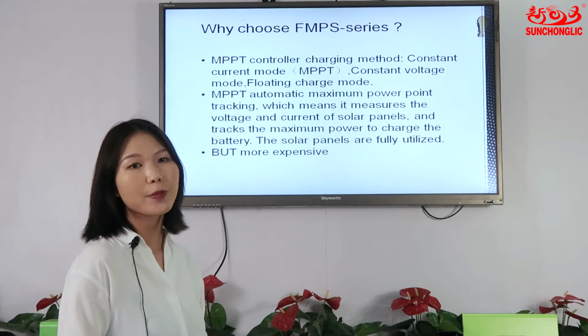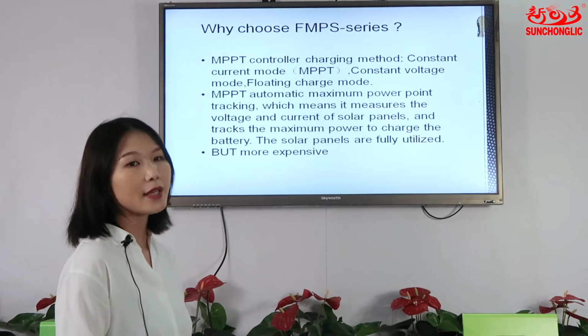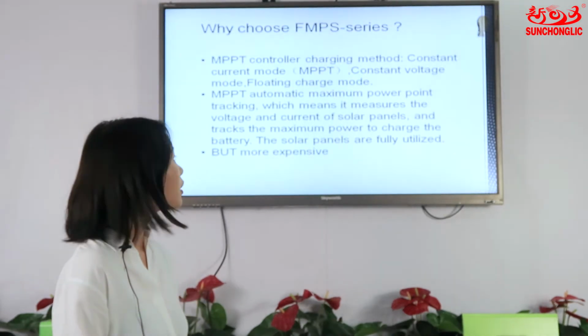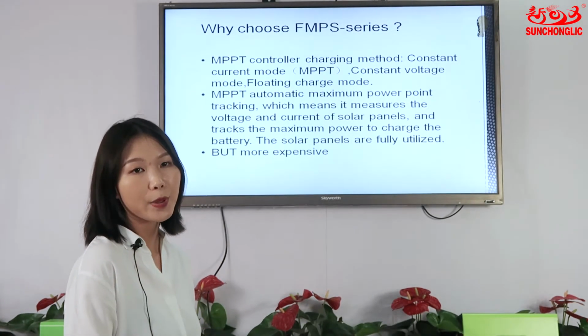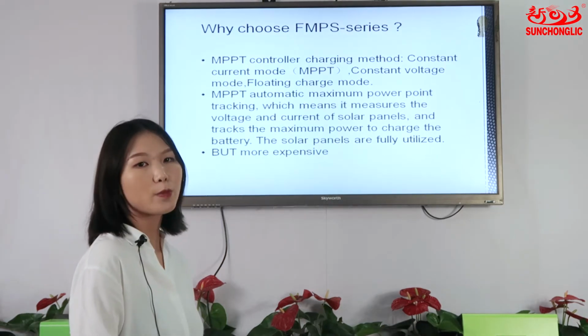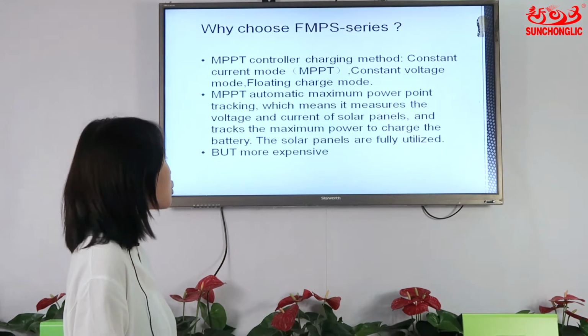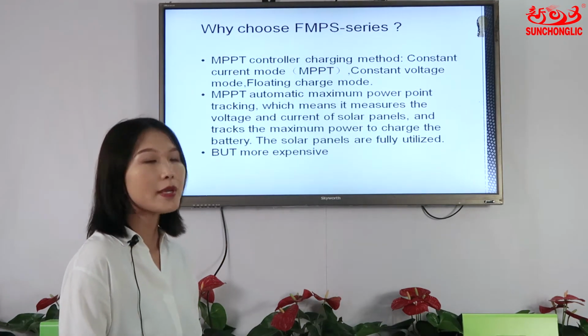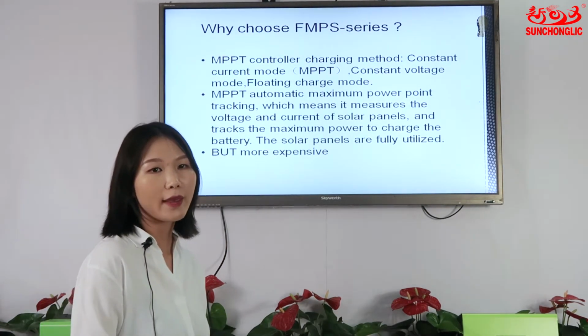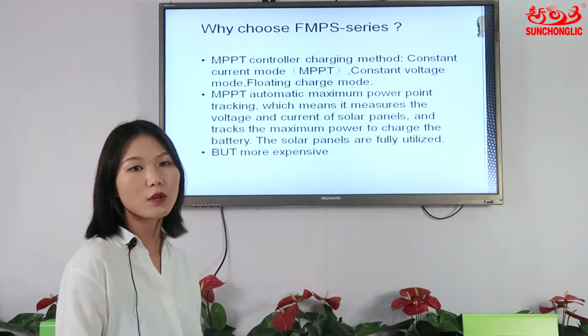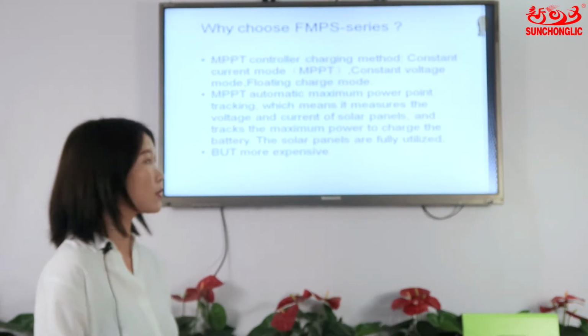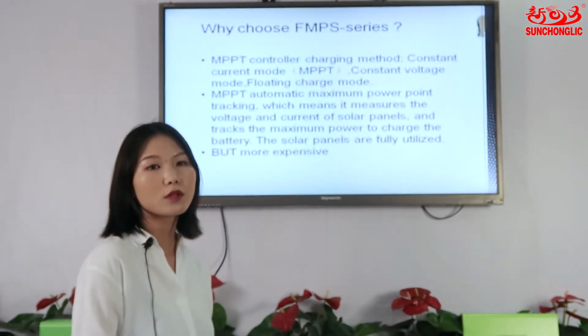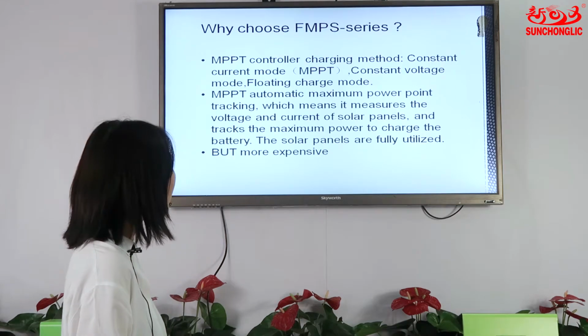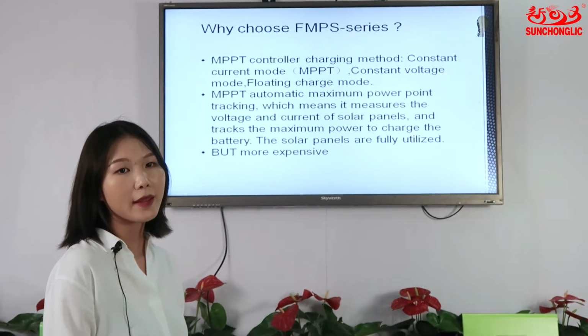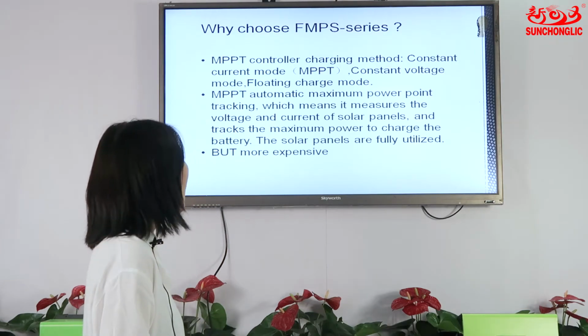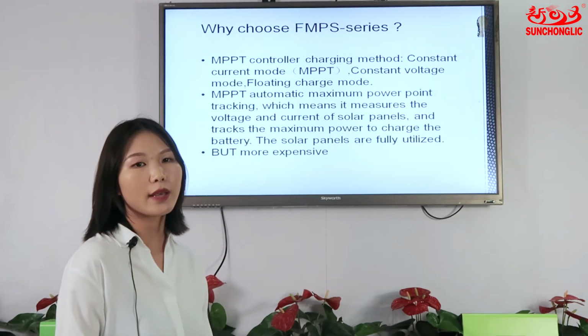Why choose the FMPS series model? The MPPT controller's charging methods are constant current mode using MPPT, constant voltage mode, and floating charge mode. MPPT stands for maximum power point tracking, meaning it measures the voltage and current of the solar panels and tracks the maximum power to charge the battery. In this system, the solar panels are fully utilized, but the MPPT controller is more expensive.